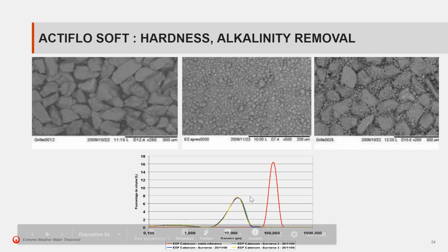If you look at them on the granulometric analysis, you have the particles of microsand here, and you have the pellets of CaCO3. It's really two different compounds that are treated well separately, and that's why with the hydrocyclone we can separate these very efficiently because the cutoff size is there. So this goes in the overflow in the sludge, and this goes in the underflow back into the tank.